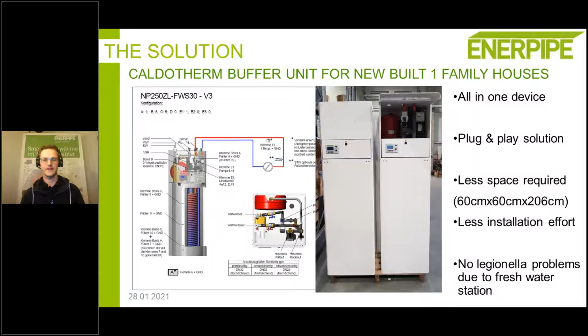Another thing is possible with such a concept: not just reducing pipe sizes, but optimizing the loading of your buffers, something David will explain afterwards in detail. You have to install not just pre-insulated pipes but also some cables for communication. So if one house has, for example, some heat demand in summertime, you can load the other houses at the same time, and afterwards the pump can be switched off instead of pumping hot water through the network all the time.